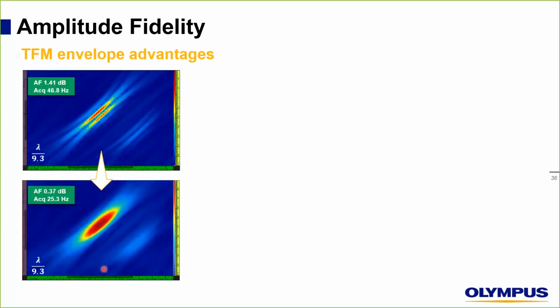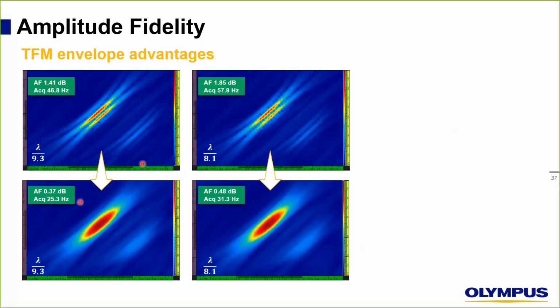So let's start with this one. We have an amplitude fidelity of 1.41 here, an acquisition rate of 46, and we are using a resolution of 9.3 points per wavelength. Applying the envelope here would improve the amplitude fidelity value to 0.37 dB. Of course, the acquisition rate will be reduced. Here we have 1.85 dB as amplitude fidelity. We apply the envelope, it became 0.48 dB as well. Again, the acquisition rate will drop a little bit, and of course, we are maintaining the same grid resolution here.